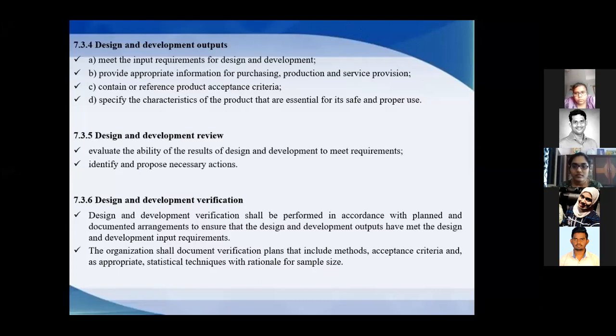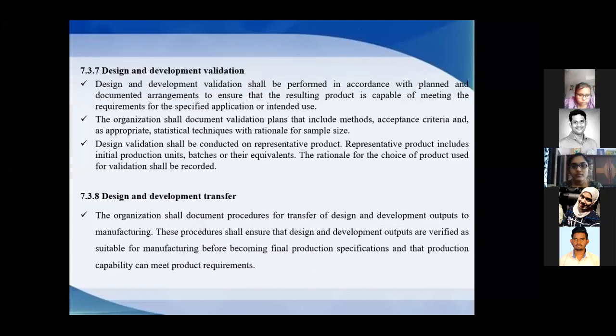The organization shall document the verification plans, which include methods, acceptance criteria, and appropriate statistical techniques with rationale for the sample size. And coming to design and development validation, it includes performance in accordance with the planned documented arrangements to ensure the resulting products are capable of meeting requirements for the specified application or intended use. The organization shall document the validation plans that include the methods, acceptance criteria, and appropriate representative products.